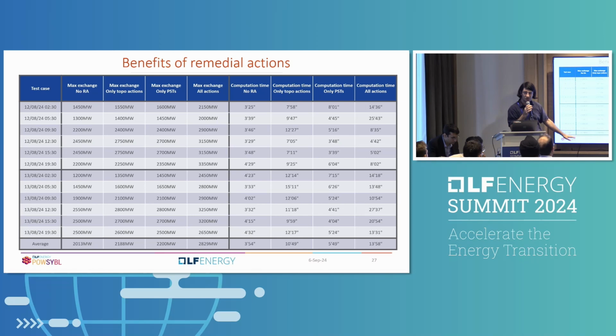With no remedial actions at all, we usually get a max exchange from France to Spain of 2,000 megawatts. When we add either topological actions or PSTs, we gain another 200 megawatts. What's really interesting is that we really need both topological actions and PSTs together to see an important gain on the exchange — in total we gain 800 megawatts when we optimize both together.